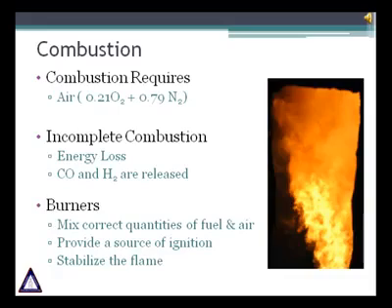But it is undesirable to operate with less than stoichiometric combustion air, as it will lead to heat loss and release of carbon monoxide and hydrogen. These last two are combustibles and could burn in the convection section, causing damage to the tubes and fins. Your aim should be complete combustion, and then, excess air reduction.